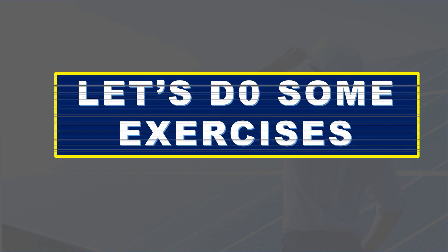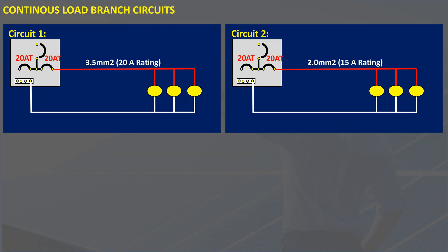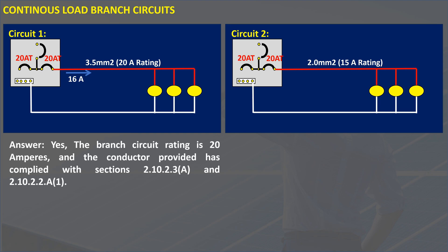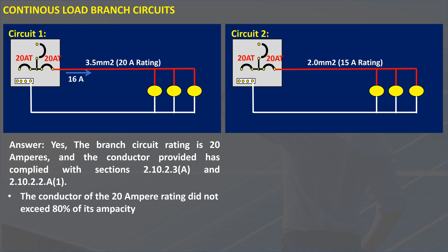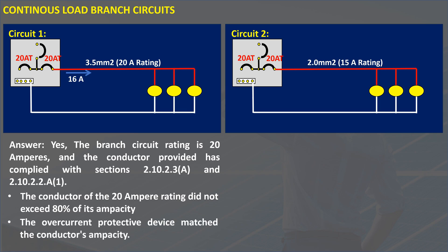Let's do some exercises. A 16 amperes continuous load is connected to a circuit rated at 20 amperes. The conductor provided is rated at 20 amperes, as shown in circuit number 1. Is this circuit compliant with the code? Yes. The branch circuit rating is 20 amperes, and the conductor provided has complied with Sections 2.10.2.3 A and 2.10.2.2 A1. The load on the 20 amperes rated conductor did not exceed 80% of its ampacity, and the overcurrent protective device matched the conductor's ampacity.